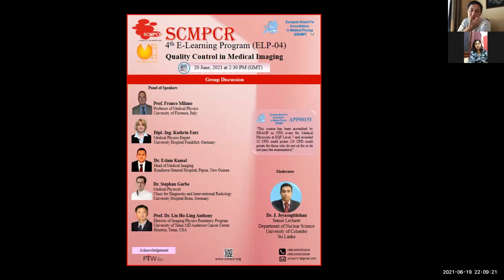For clinical applications, the way to make sure quality is optimal is very simple. We ask radiologists to review. It's not determined by physicists. Whether the image quality is optimal, you want the radiologist to confirm. So we routinely have a QC meeting with radiologists to review image quality in different protocols. During that meeting, they can tell us whether the image quality is good or not, and what their desire is, whether they want better contrast or better resolution or better SNR. Then we can try to fine tune our protocol. So that's about image quality optimization.